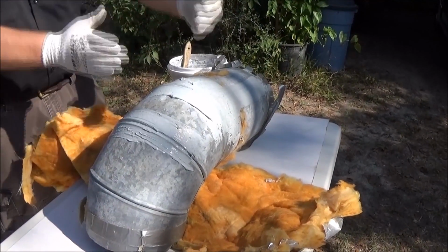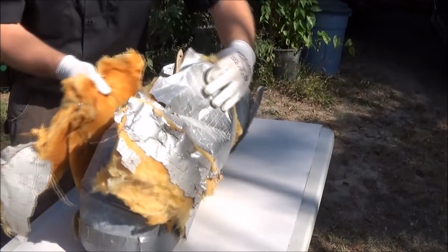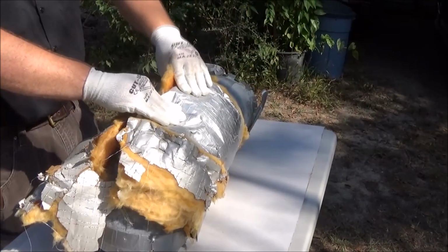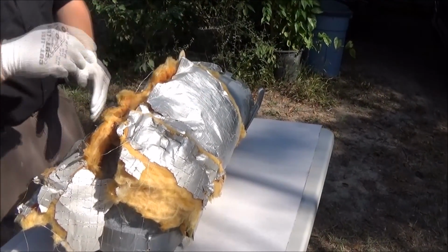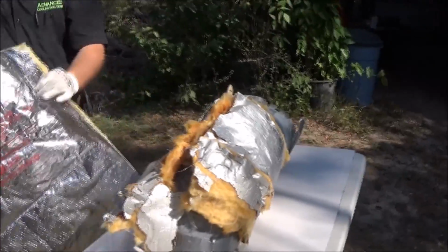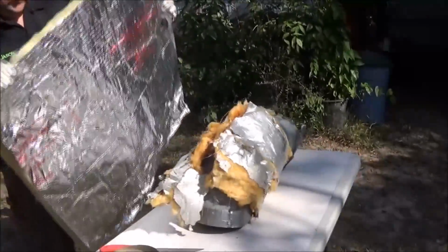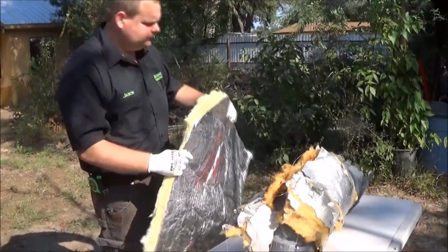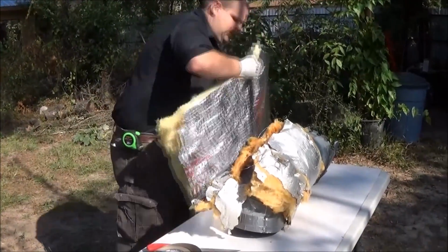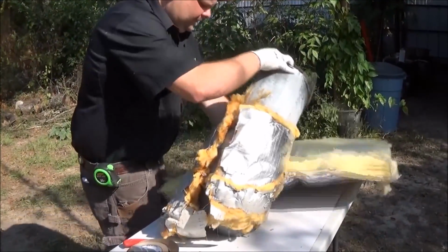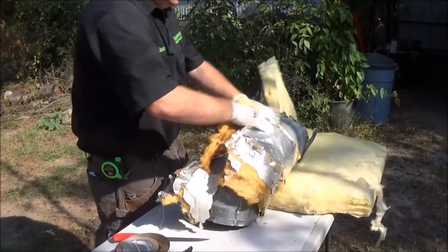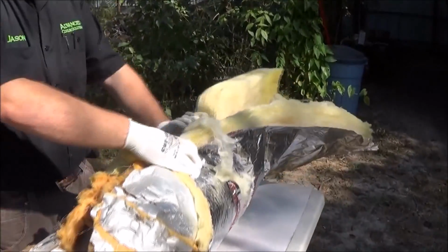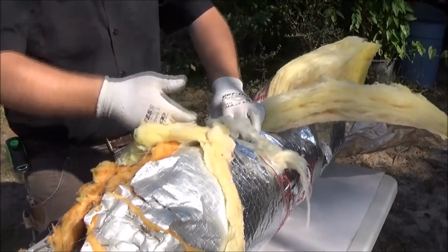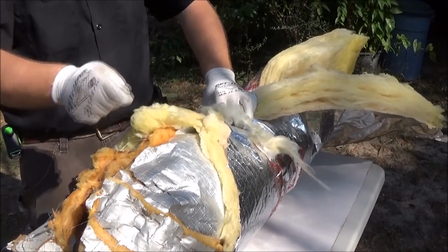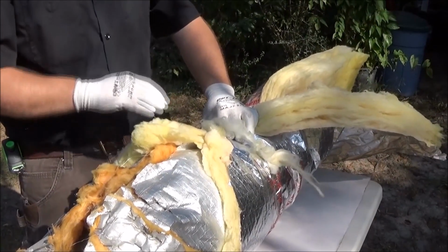Once we sealed the ductwork, we pulled the insulation back, taped it in place, and then overwrapped it with duct wrap, which comes in 4-foot sheets. We cut it to fit, and the overwrapping basically made it look very similar to this. We applied our tape, squeegeed it down, and made a permanent fix.